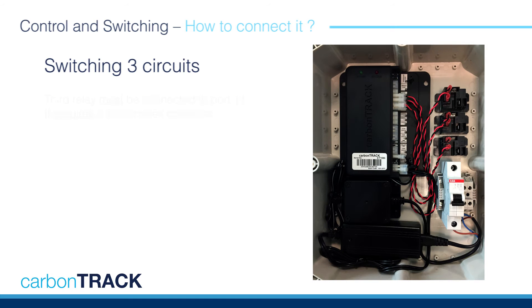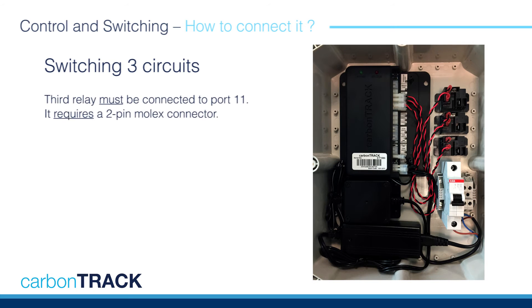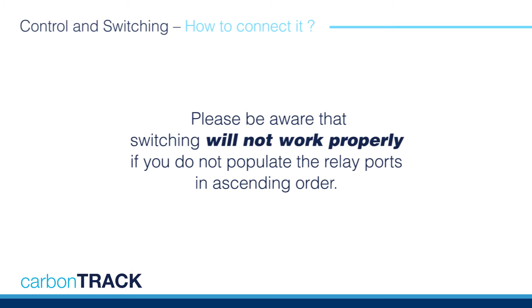If you are switching three circuits or loads, the third relay coil must be connected into port 11 of the CT100i using a 2-pin Molex connector cable. Please be aware that switching will not work properly if you do not populate the relay ports in ascending order.